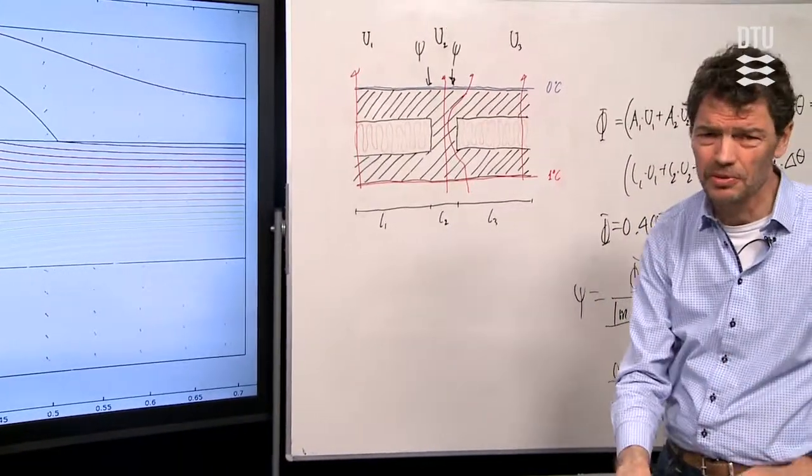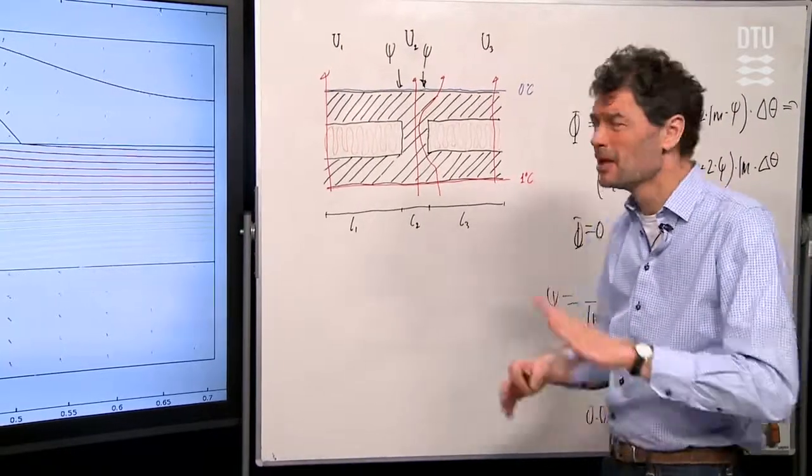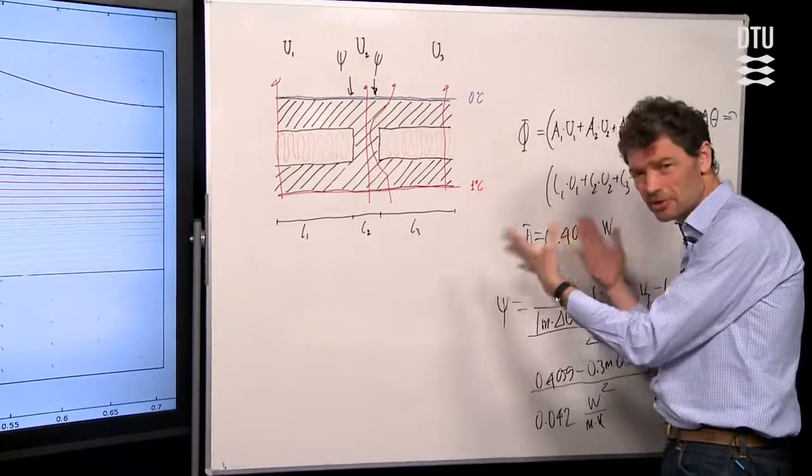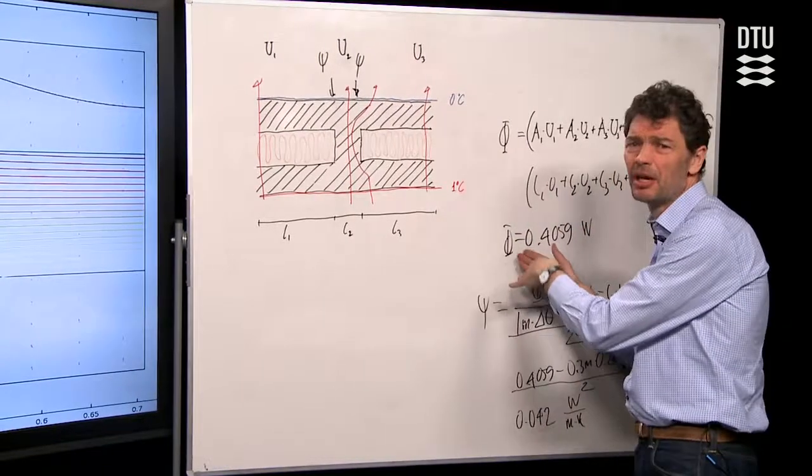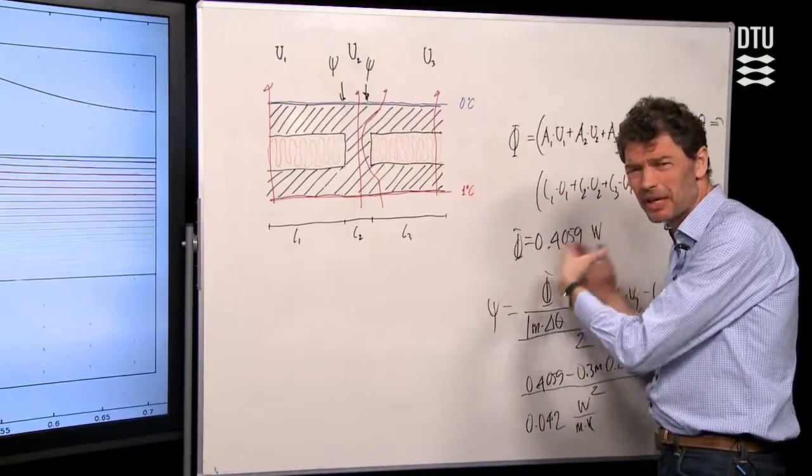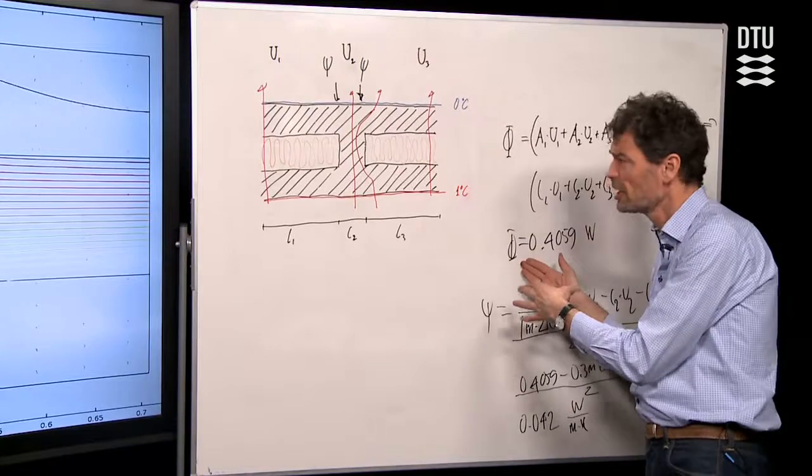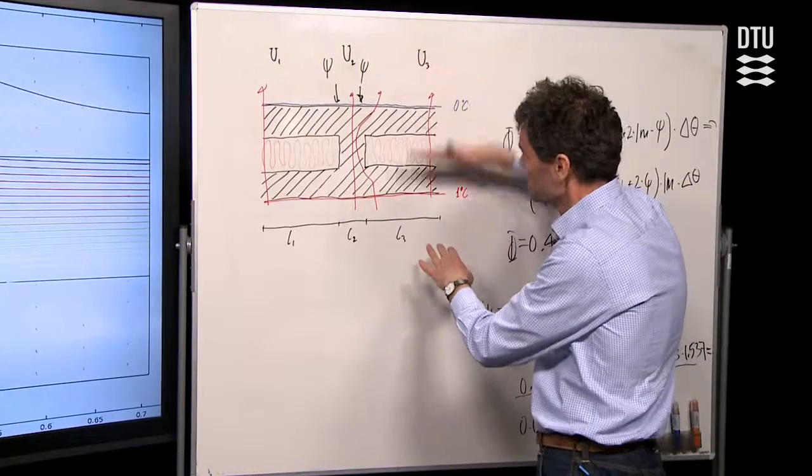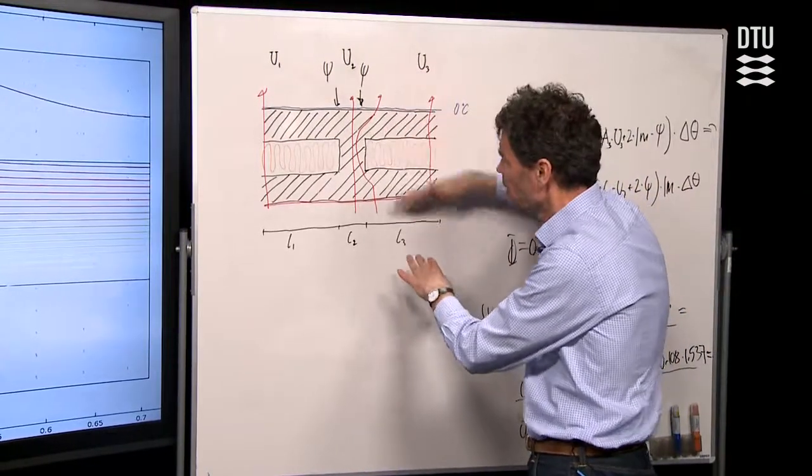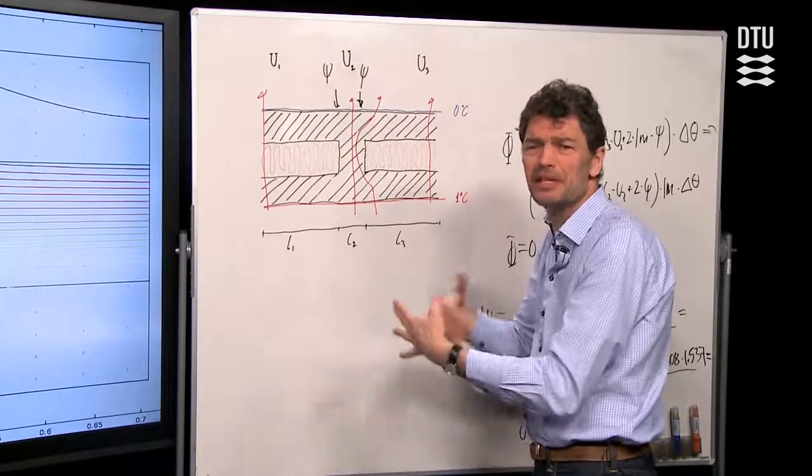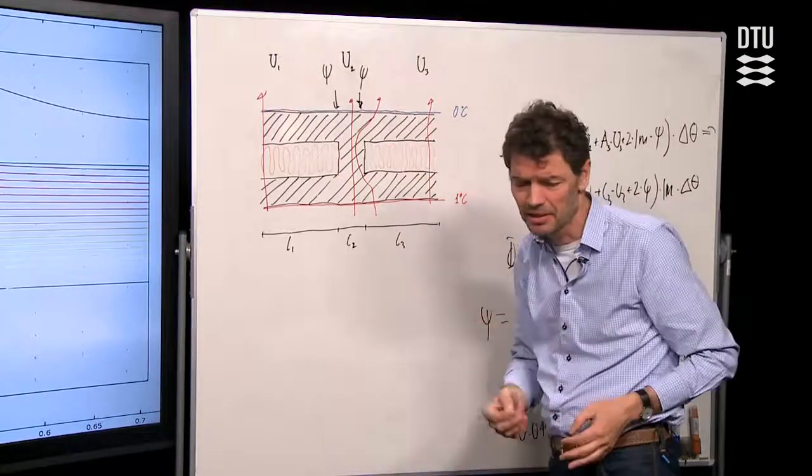So that was how to calculate a Psi value for this special geometry in this case. And how you will always need to calculate Psi values. The notion is to calculate what is a real multidimensional calculated heat loss. Subtract from that those elements that would normally be seen for one-dimensional flow. And then Psi expresses kind of the extra that you will get.